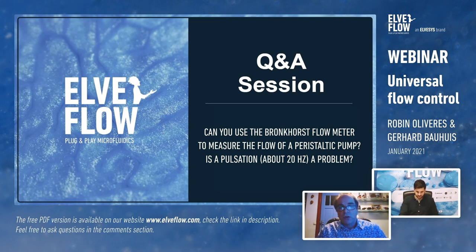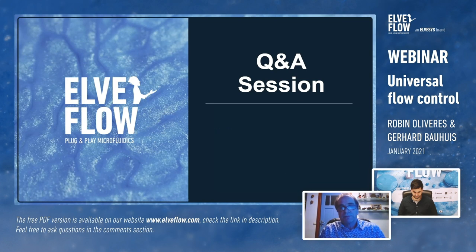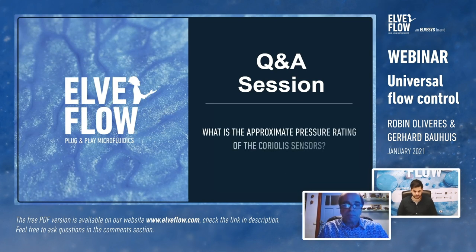Bronkhorst does have controllers that can regulate pumps and partially reduce pulsation, but some pulsation will always remain. On pressure rating: the Coriolis sensors and meters are rated at 200 bar, so they can definitely be used with Elveflow equipment which goes up to 10 bar.